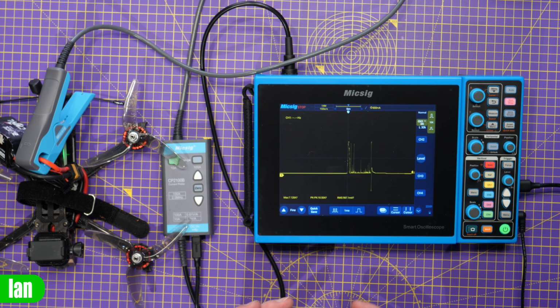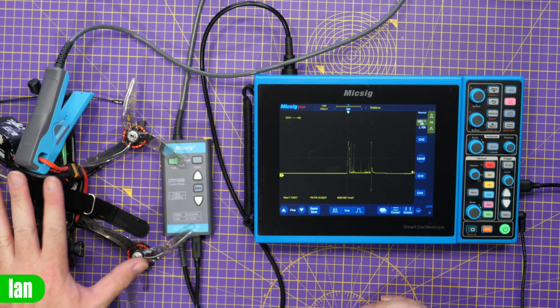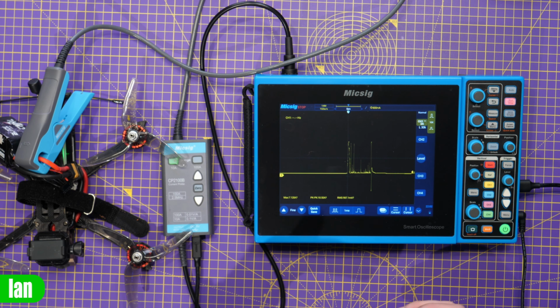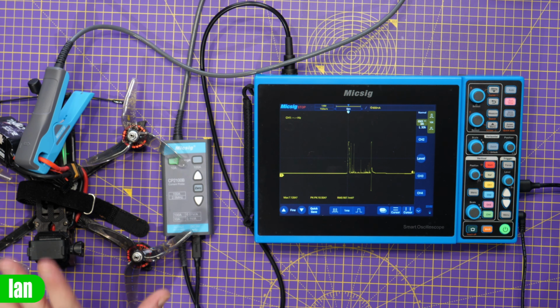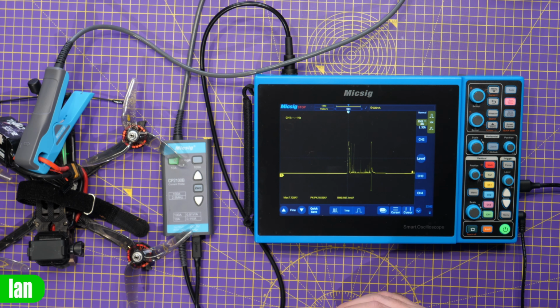The last thing we're going to do quickly is just take a look at some inrush current measurements with the probe. Now, I've got it hooked up to a quad on the bench, we've got it on the battery, and what we're going to do is put it in single shot mode on the scope, or single capture, and then we'll plug the battery in, and that will allow us to have a look at what kind of current spikes we get when we actually connect the battery up, and just giving you an idea of the kind of numbers that you can see even on things like this. And we'll take a look at some goggles and stuff now as well from the FPV side of things.